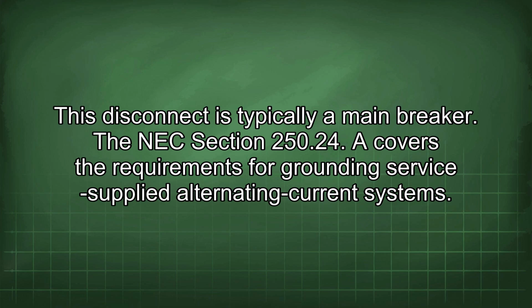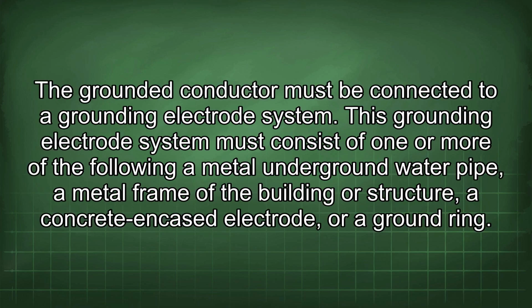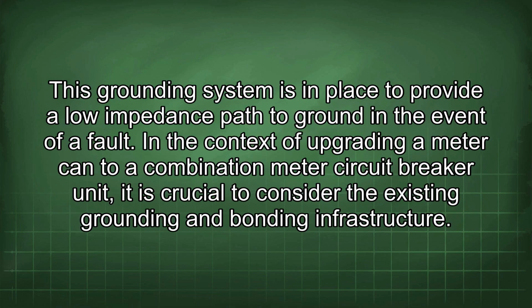The NEC Section 250.24 covers the requirements for grounding service-supplied alternating current systems. The grounded conductor must be connected to a grounding electrode system. This grounding electrode system must consist of one or more of the following: a metal underground water pipe, a metal frame of the building or structure, a concrete-encased electrode, or a ground ring. This grounding system is in place to provide a low impedance path to ground in the event of a fault.